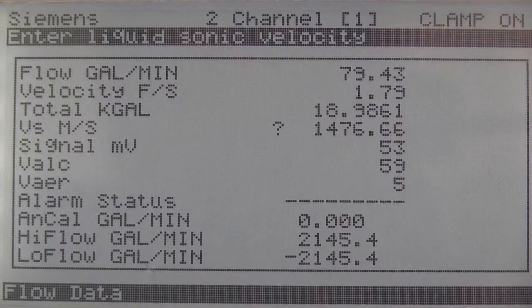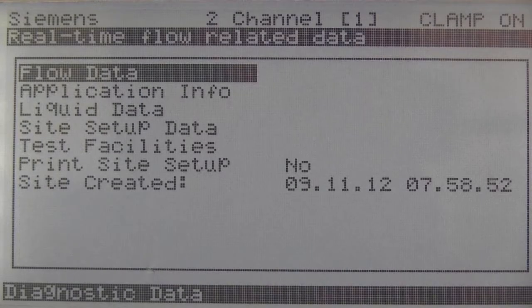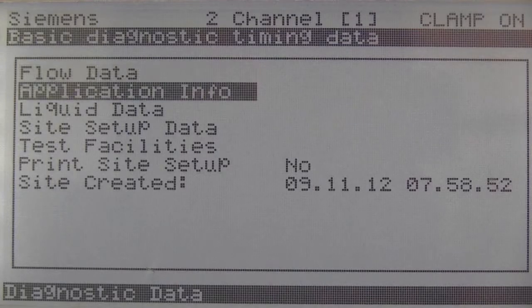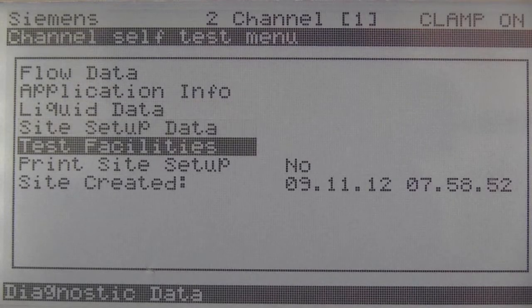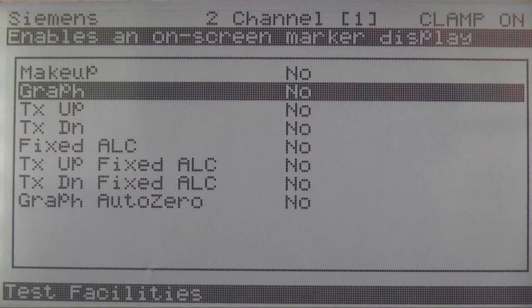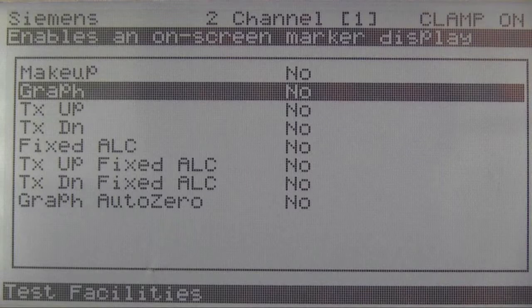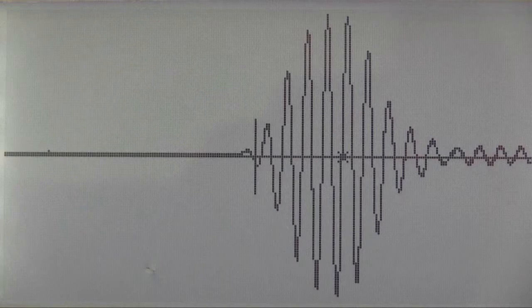Now let's confirm the timing measurement, which also gives us the opportunity to evaluate another important performance indicator, our sensor signal wave shape. Let's exit the flow data category and scroll down to test facilities, where we can access graph mode. Here we can see a graphic image of our sensor signal wave shape in real time, and also verify our transit time measurement.